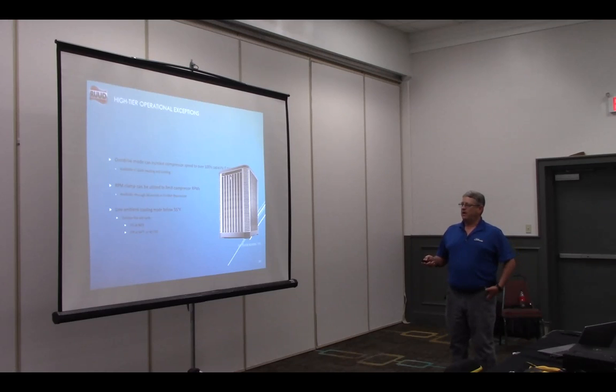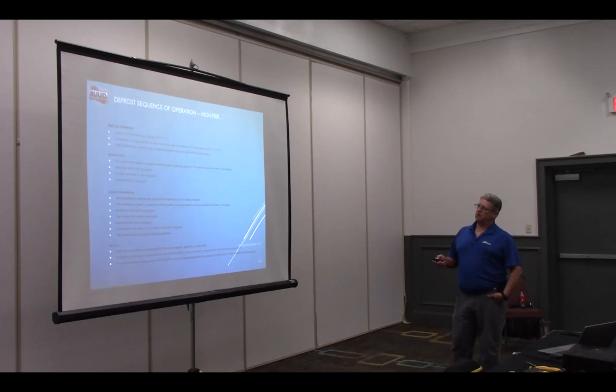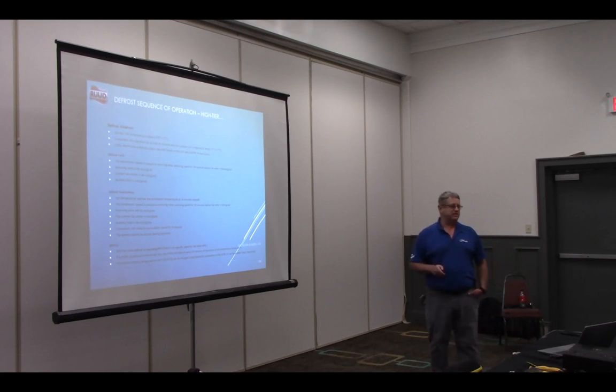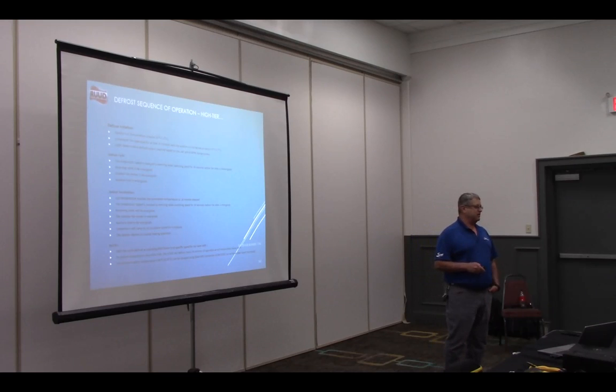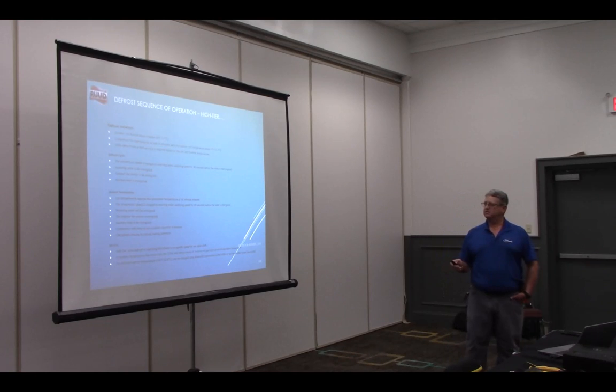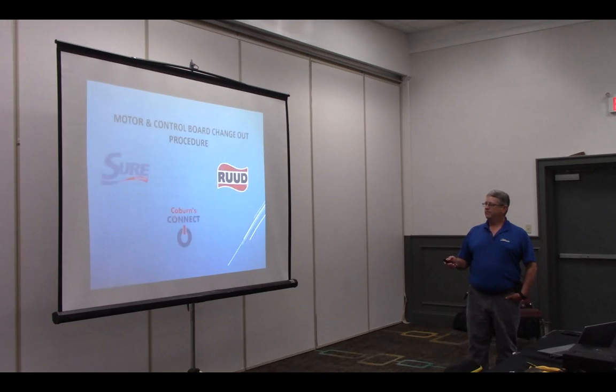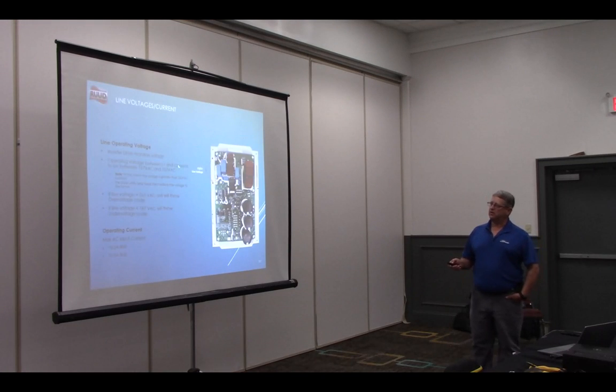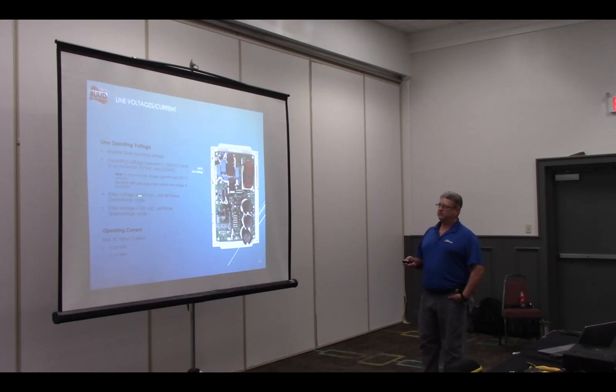We talked about our low ambient cooling outside. We talked about our defrost initiation in our high temp. It's the same for the mid-tier and high-tier. It's all the same sequence, and you can put it in demand defrost by holding that test button down for 5 seconds. Okay. And our high-tier troubleshooting has the same voltages here, between 197 and 253. At 265 it throws an alarm, and at 187 it throws an alarm.